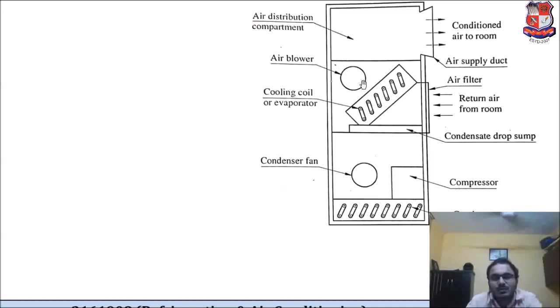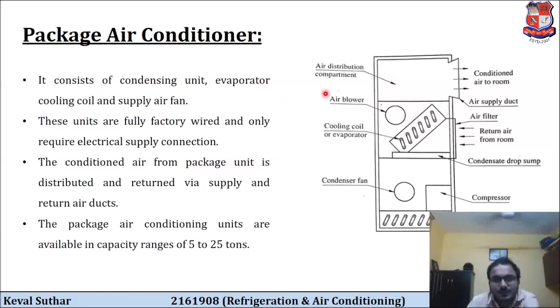Okay, now it consists of the condensing unit, that is this bottom part, the evaporator, that is the middle part, and the supply air fan. These units are fully factory wired and only require an electrical supply connection. The conditioned air from the packaged unit is distributed and returned via supply and return air ducts. The packaged air conditioning units are available in capacity ranges of 5 to 25 tons. So this is all about the packaged air conditioner.